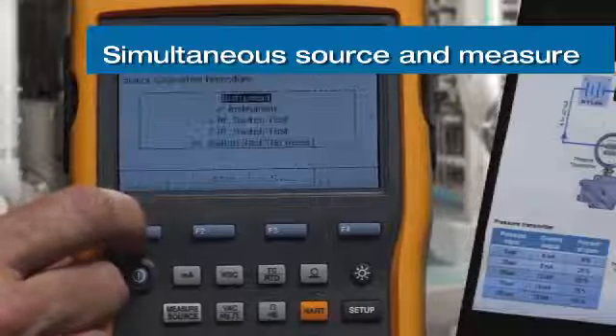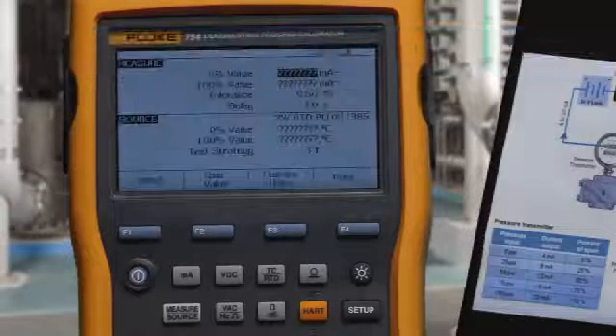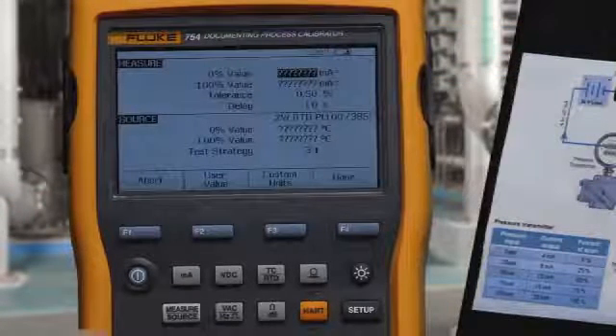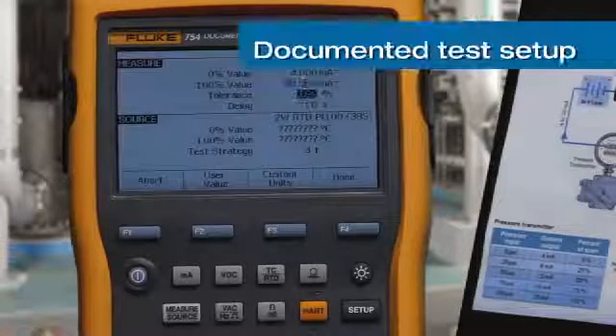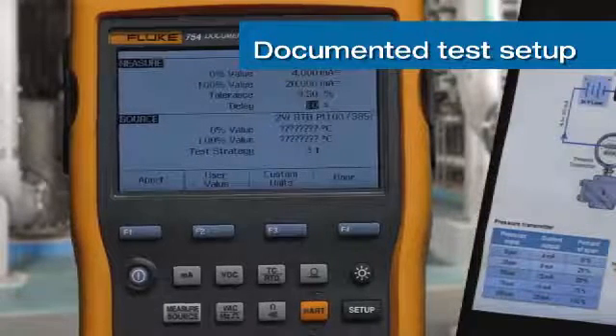We document the calibration as found for an instrument. We're going to measure 4 to 20 milliamps to a test tolerance of 0.5 percent while sourcing 0 to 300 degrees C.